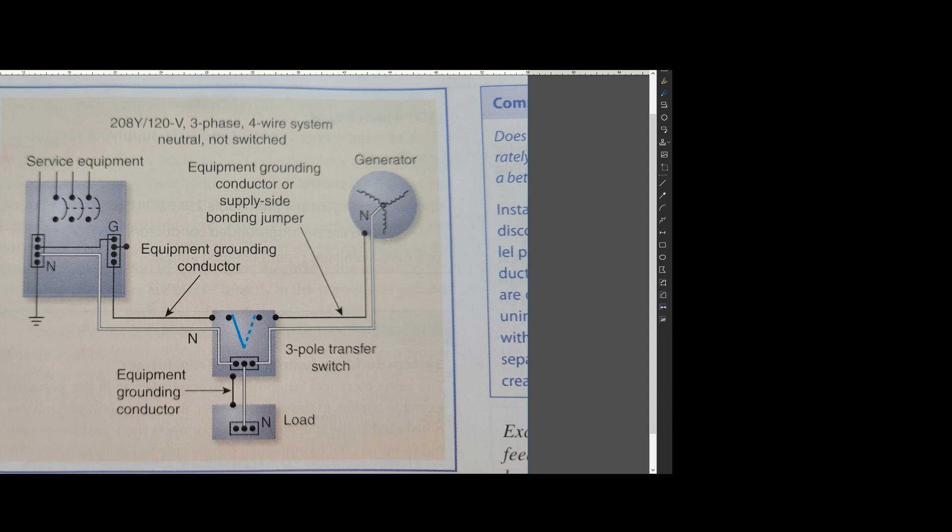In this case, this entire setup is considered as one single system. So the neutral to ground bonding jumper at your generator will need to be removed because your electrical panel already has this installed here. By code, only one bonding jumper is allowed per electrical system.